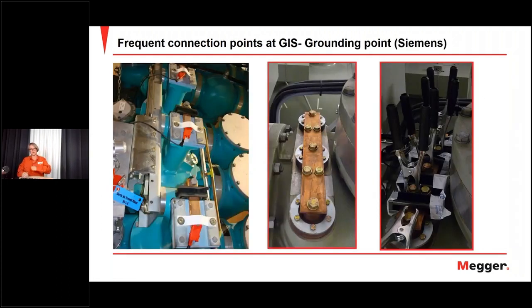So how is it done? We often access the other ground points. You have a Siemens circuit breaker here, and I think that was a Siemens as well, this one, right? And here you see the timing leads connected, and the timing leads also connected directly at the grounding points. And in both these situations, you see ferrites mounted here. I'm going to come back to that.